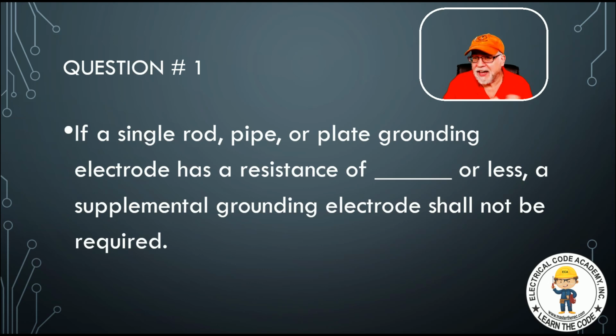And obviously, if it's there, you've got to use it. Now, you have other different types of electrodes. We'll look at each one of those really quickly so that you can have an understanding. But the question is dealing with single rod, pipe, and plate types of electrodes. Now, you are required to supplement a water pipe ground, because at some point they could change the water pipe line out and put plastic in. Now you've lost your grounding electrode system, so they require you to supplement it. It can be supplemented with any of the other electrodes, except you can't supplement it, obviously, with another water pipe ground.